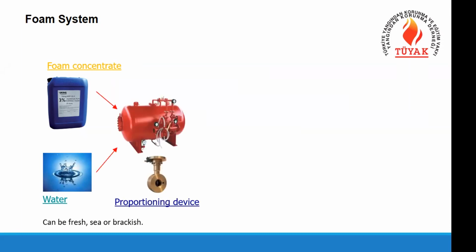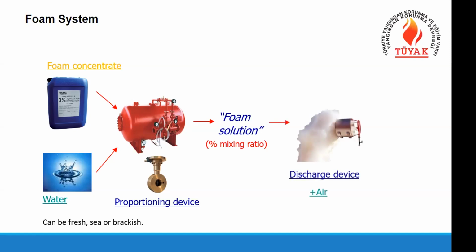By using a tank and proportioner, we have a foam solution. The foam solution includes some percentage of foam concentrate and more water. So for the 3% proportioning, we have 97% water and 3% foam concentrate. We keep this foam concentrate inside the tank, and when water passes through the proportioning device, it picks up the necessary amount of foam from the system, mixes it with the water, and sends it to the discharge devices.